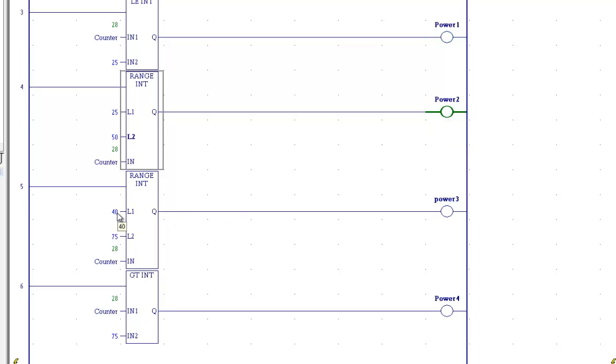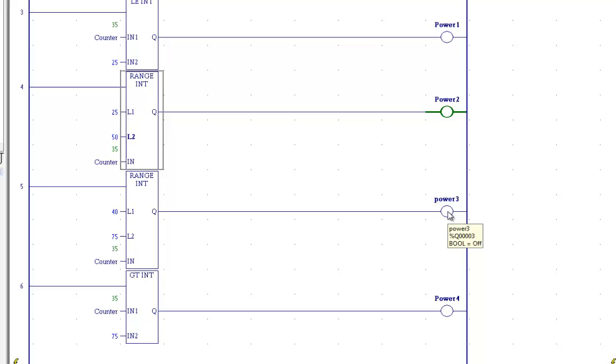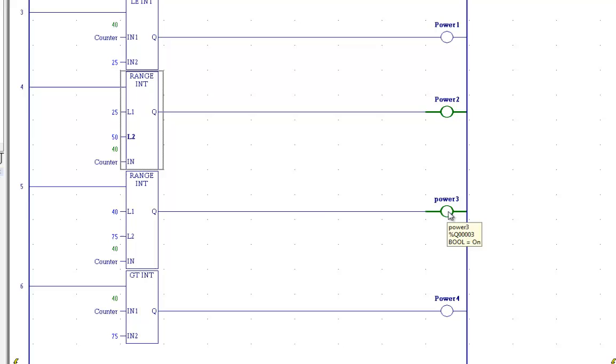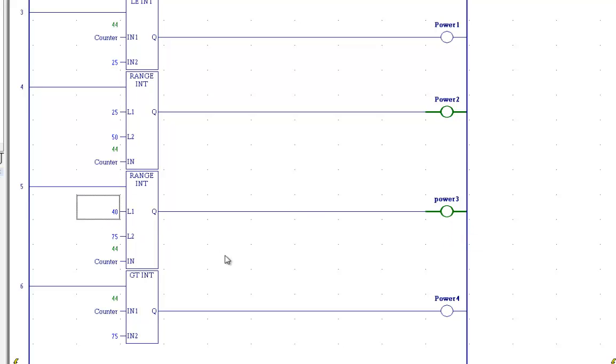Now we have an overlap here. If the range is between 40 and 75, power level 3. Now you may have a conflict, then, with two power levels being selected at the same time, at which point you would change this number right here to 51, so that you would not have any overlap.